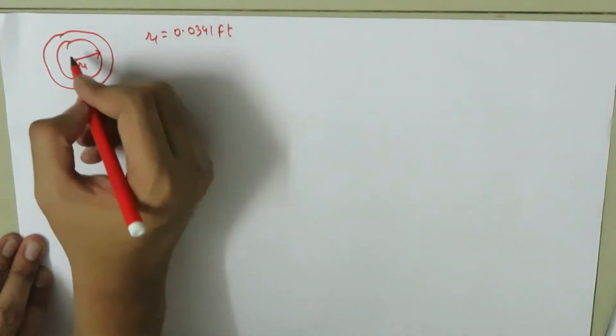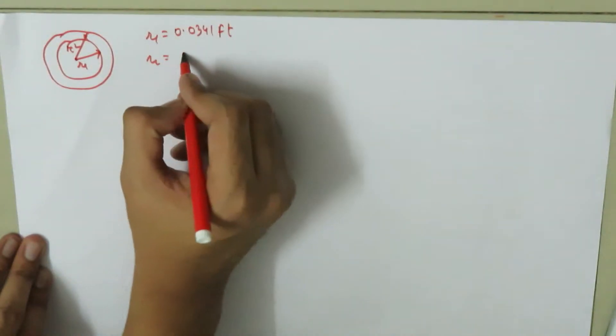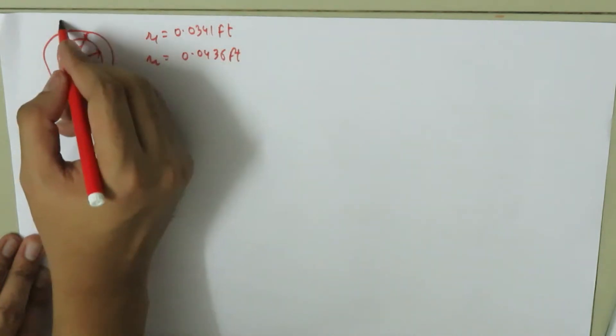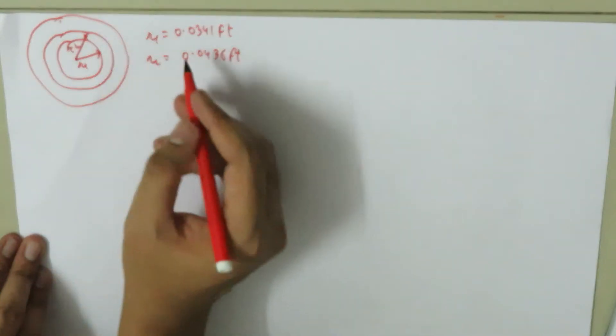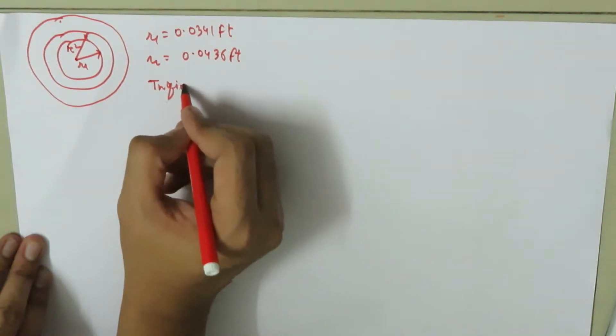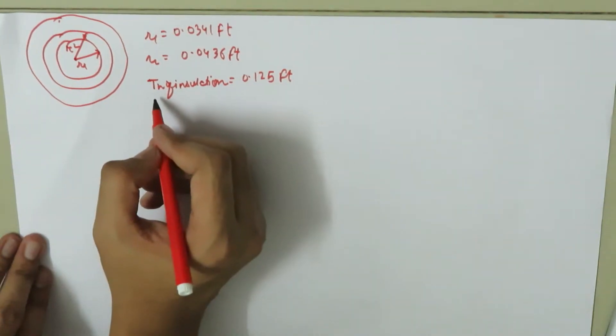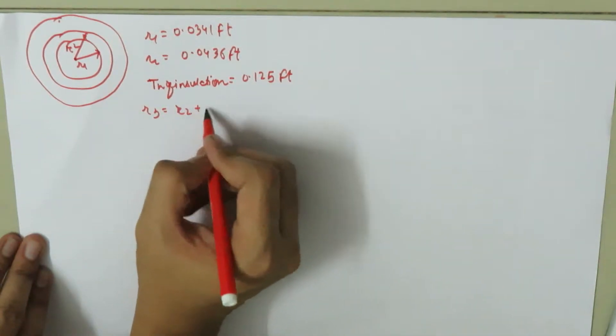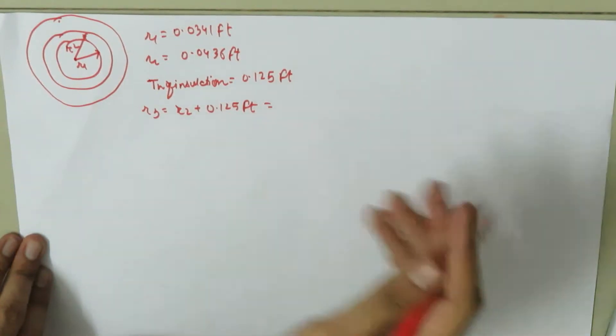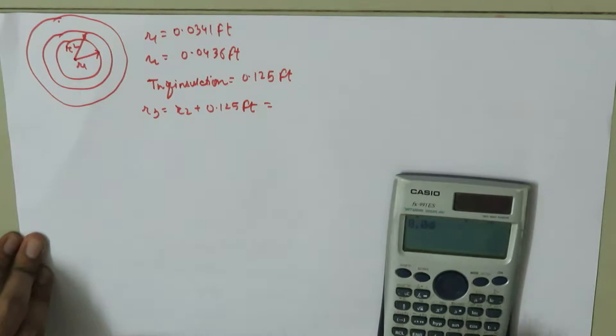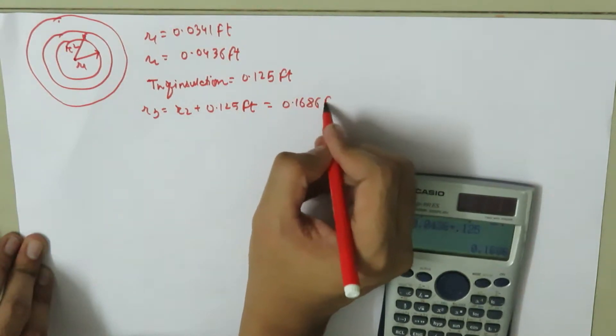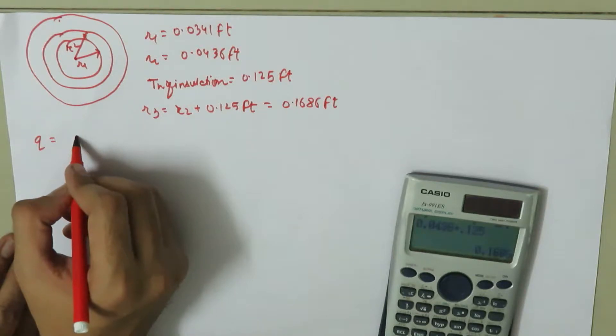Let's draw the diagram. The pipe has inside radius r1 = 0.0341 feet and outside radius r2 = 0.0436 feet. The thickness of insulation is 0.125 feet, so r3 = r2 + 0.125 = 0.0436 + 0.125 = 0.1686 feet.